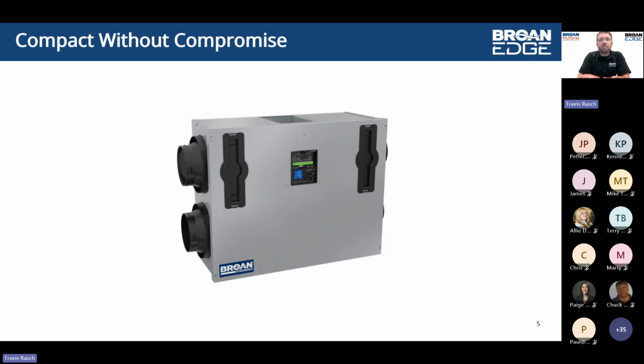As Paige mentioned, again, the main theme here for the new Broan EDGE is compact without compromise. So as you can imagine, we are looking at a low-profile design, low-profile form factor, mainly to fit in maybe ceiling bulkheads if you're in a multifamily application, or simply just take up less space overall for the multitude of different applications and install orientations that this new product has. So again, low profile, meaning less than 10 inches in height. Again, some of the key feedback we heard from the field is making sure that we stay under that 10-inch mark, again, just to fit in those tighter ceiling bulkheads as an example, to both minimize the impact of the ERV, but also maximize the ceiling heights in those types of dwellings where, again, ceiling heights can be a challenge.